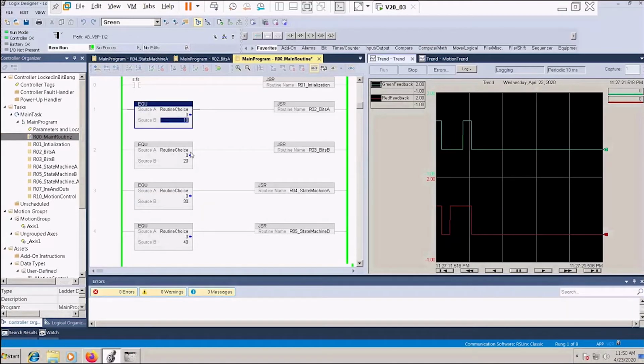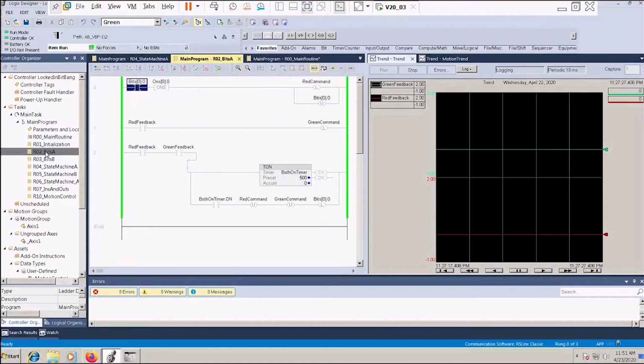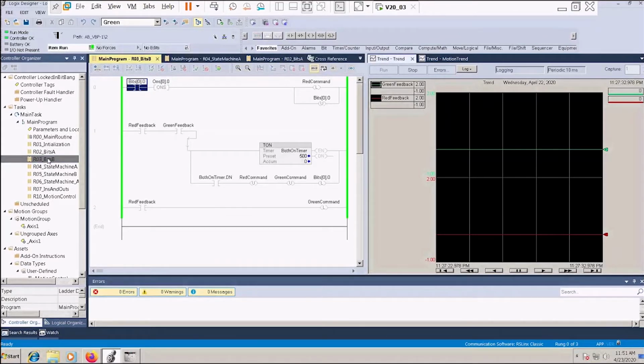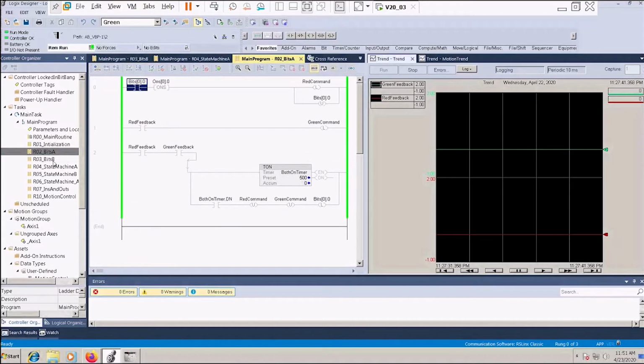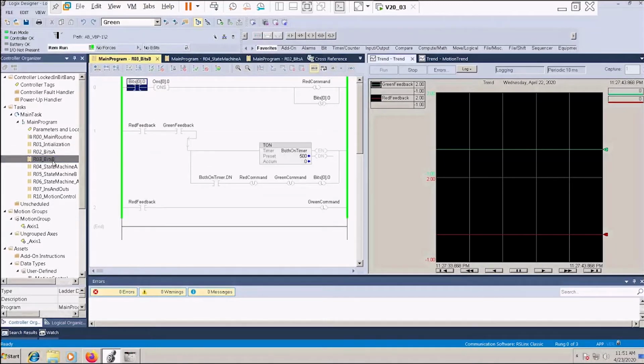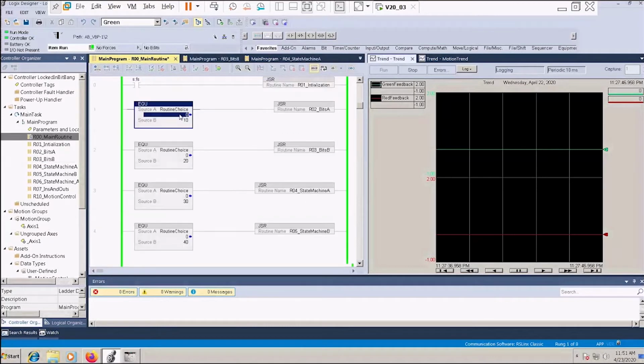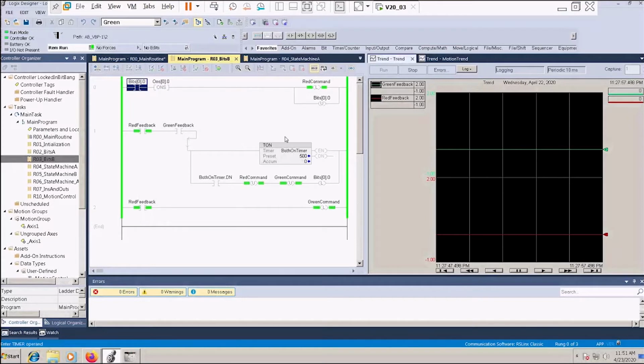I do a clearing of my bits. Now, just to prove a point, this is the bit logic, the exact same code, but the order of the rungs has been rearranged. In other words, I moved the timer up above the green command. I'm sure you guys can see that. So let's see what happens when we enable that to operate. We put a 20 in. Now we're scanning that. Start the same process. Same code, just a different order of operations.